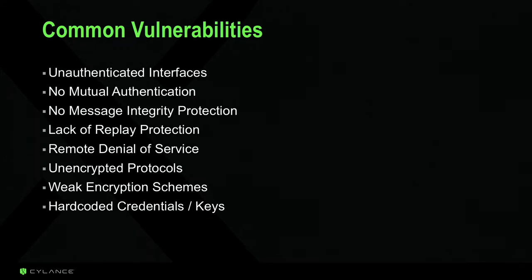Here are some findings from engagements — no vendor or device names, not to name and shame. These were found assessing for providers. Common issues include: lots of unauthenticated interfaces, lack of mutual authentication, no message integrity protection, lack of replay protection, remote denial of service — devices fall over from a stiff breeze — either unencrypted protocols or really weak encryption schemes, and a lot of hard-coded credentials and keys.